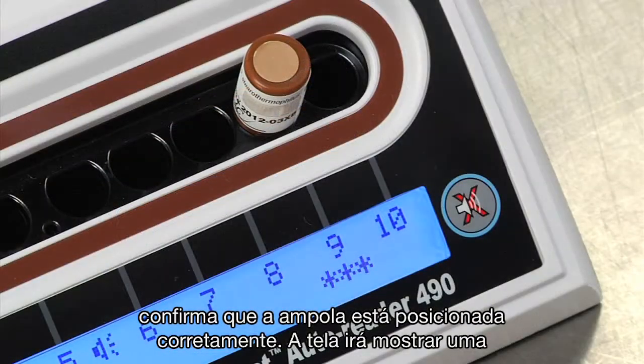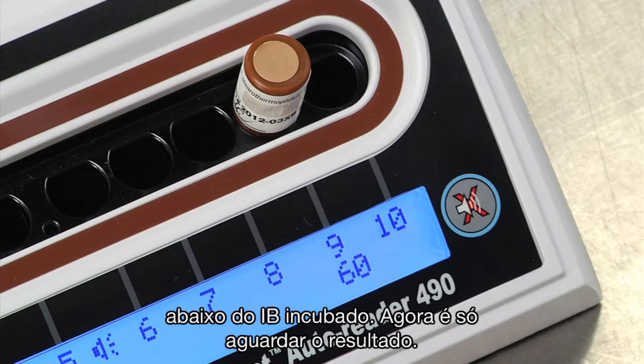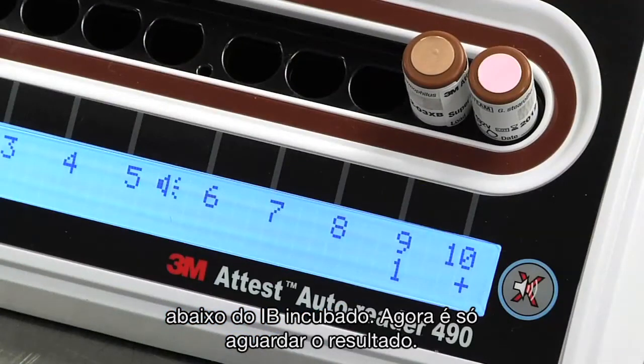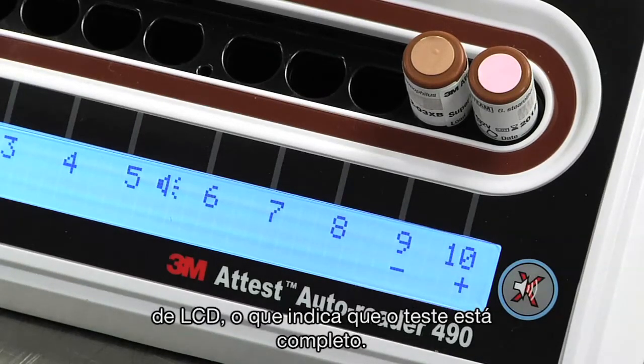The Auto Reader LCD panel will display a series of asterisks, then the remaining incubation minutes right below the incubating BI. Now all you need to do is wait for the result. Never remove an incubating Attest Super Rapid BI until you see a plus or minus sign on the LCD panel, which indicates the test is complete.